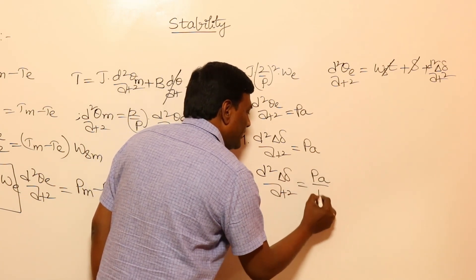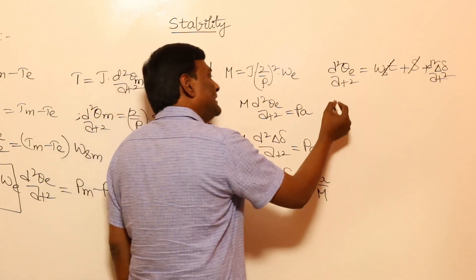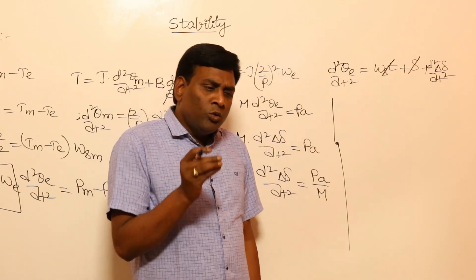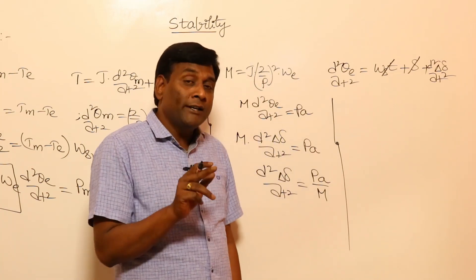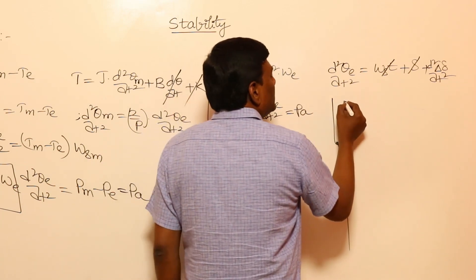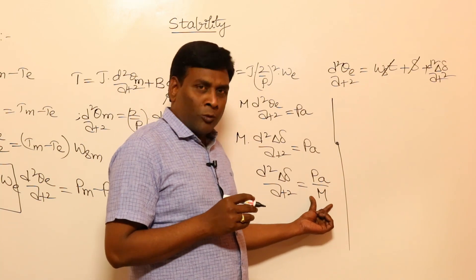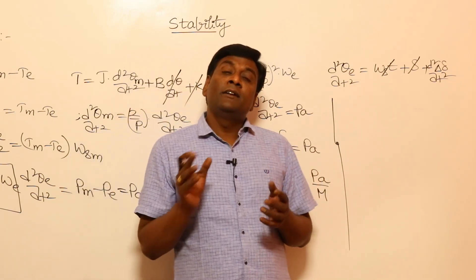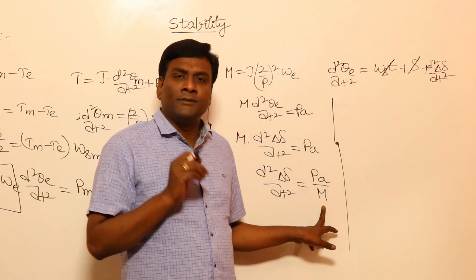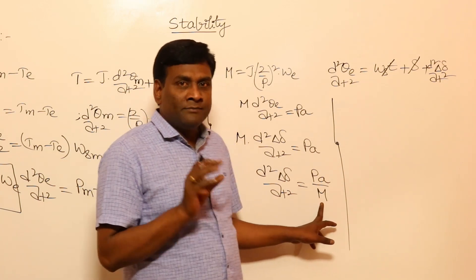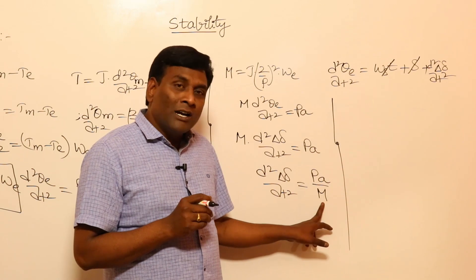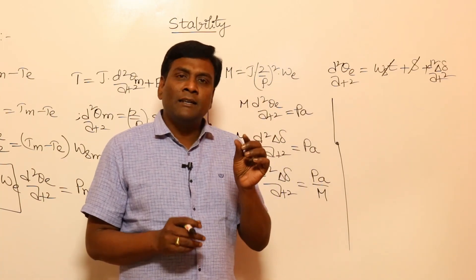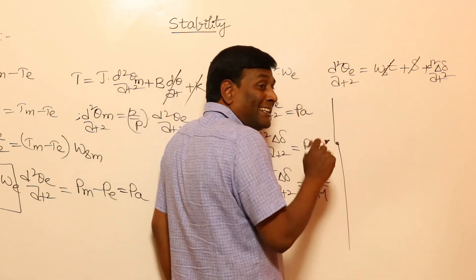Now dimensions become important. The problem with M is that its variation is large — it varies with load percentage, rotor type (cylindrical vs. salient), and other factors. We want to convert from large M variations to smaller variations using the inertia constant H, so we can treat it as a near-constant machine parameter.